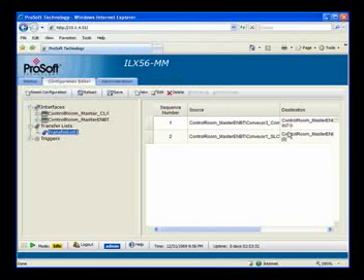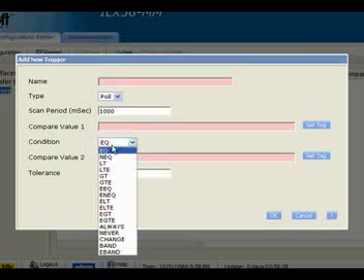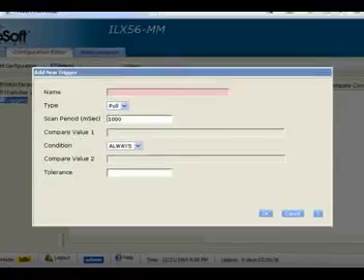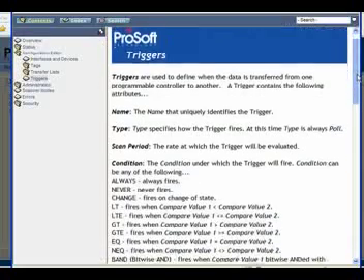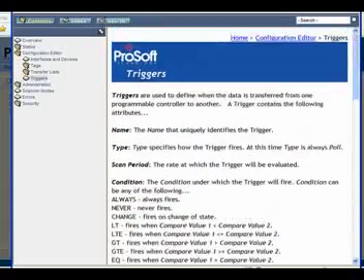Now we need to add triggers for our transfer list — triggers execute the transfers. I'll select Triggers and click New. There are many different trigger options. I'll name this Trigger 1 and go with the default poll type. The compare values won't be used for this. There are several different conditions available — I recommend checking out the help file for descriptions of every condition. For now I'm going to select 'Always,' which means this trigger will execute as fast as possible based on the scan period. That all looks good, so I'll click OK.